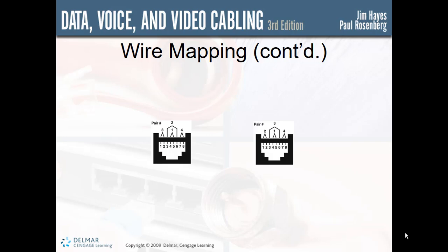And swapping those pairs makes no difference in performance. It's simply a different color code convention adopted by various vendors. So it's the white-orange pair and the white-green pair, so your wires 1 and 3 and 2 and 6 would then be switched. Whichever version you're going to use, it must be used throughout the entire installation to prevent problems.